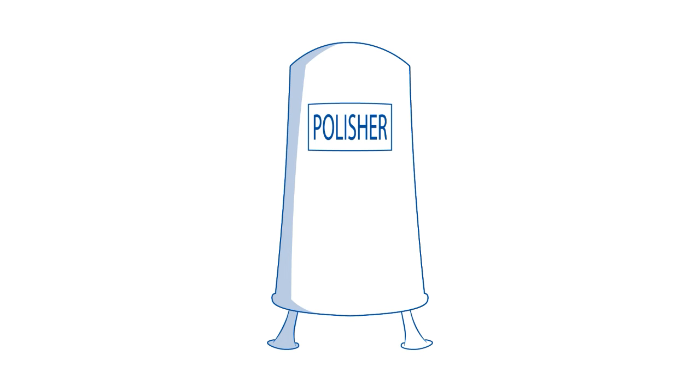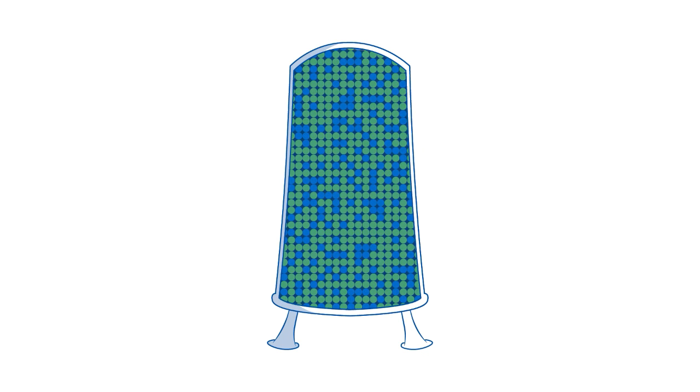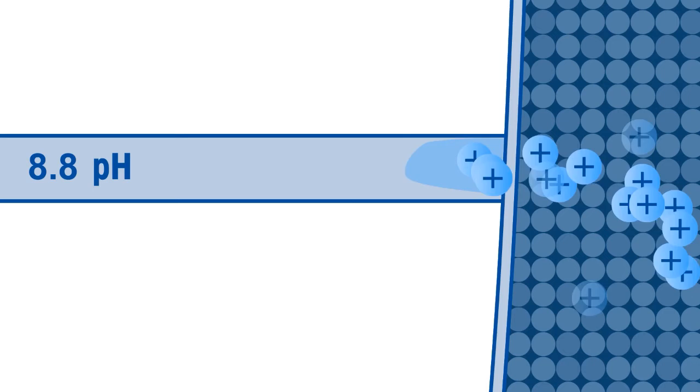This makes calculated pH based on conductivity significantly more accurate. However, with major contamination, such as when a condensate exchange polisher's resin is exhausted and an acid leak occurs, the pH would drop below 7.